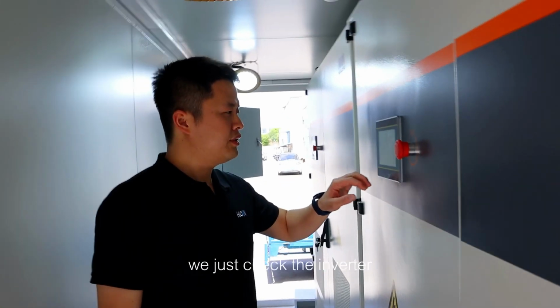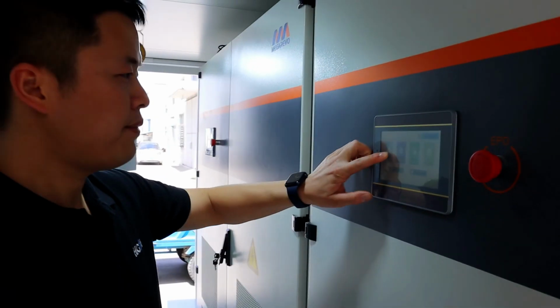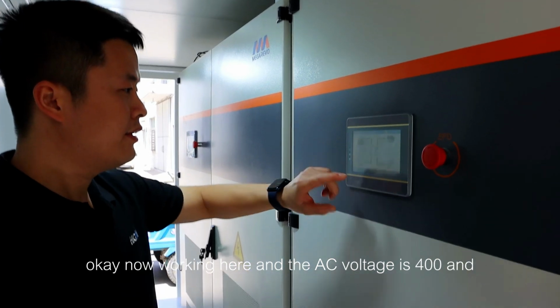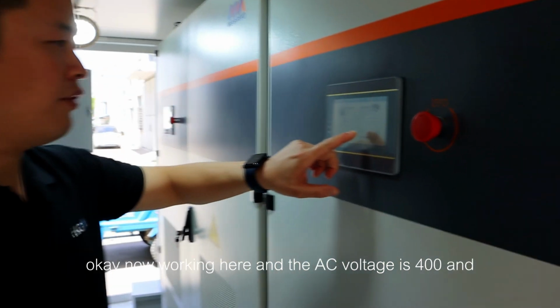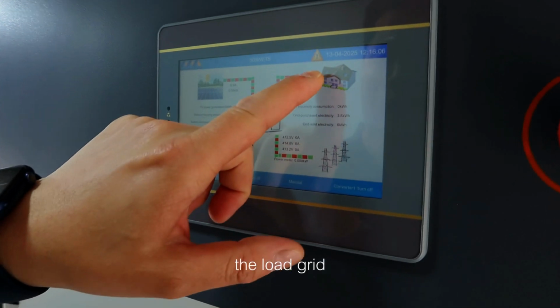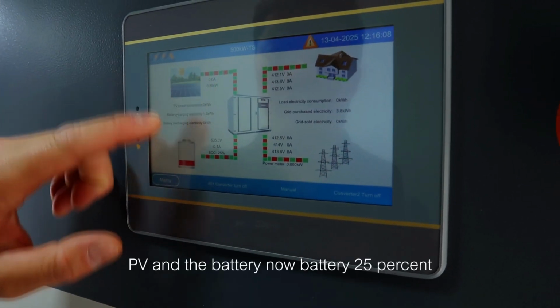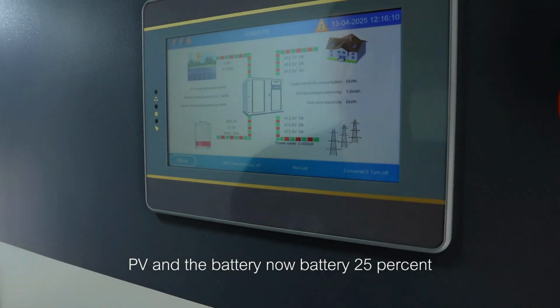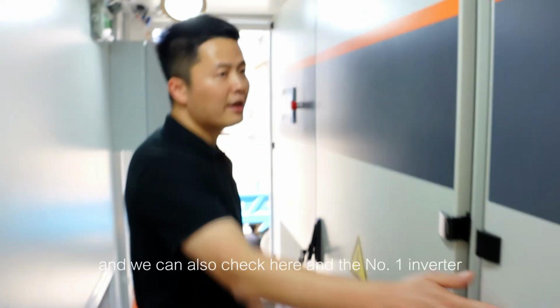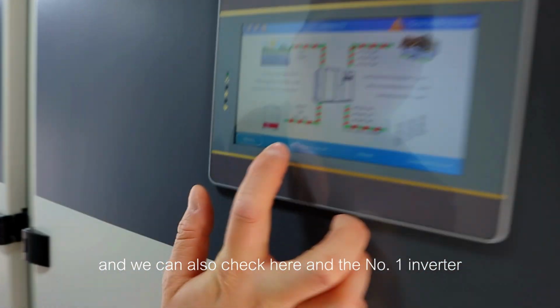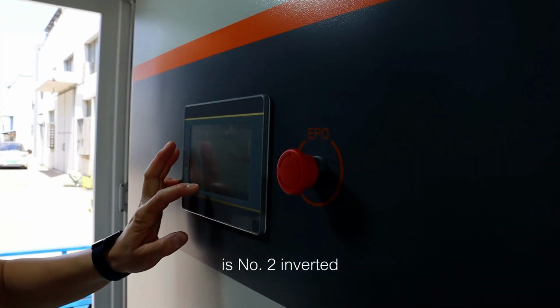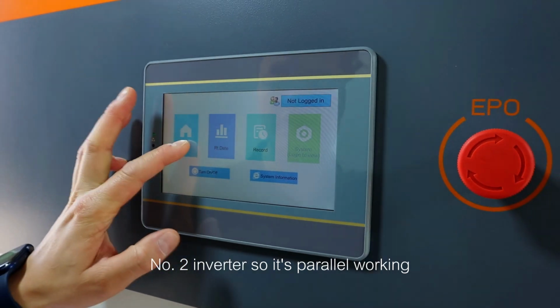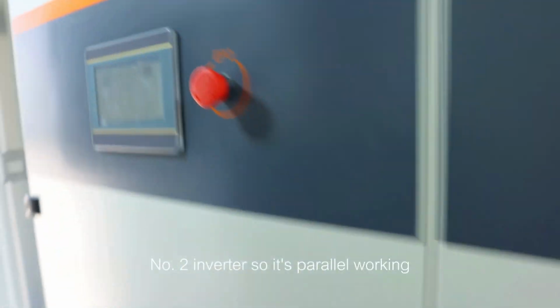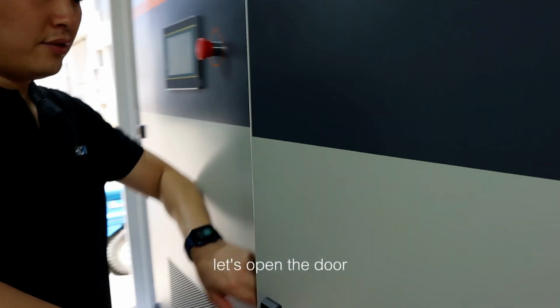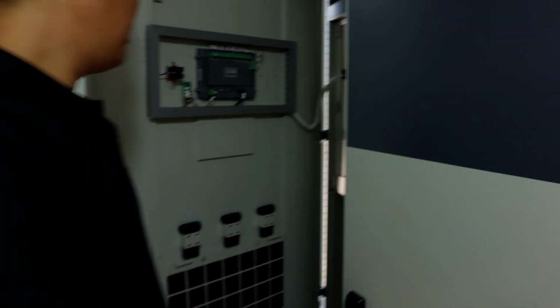Okay, we just check the inverter. Now it's working here, and the AC voltage is 400. The load, grid, PV, and battery, the battery is at 25%. We can also check here, this is the number 1 inverter and this one is the number 2 inverter, so it's parallel working. Let's open the door.